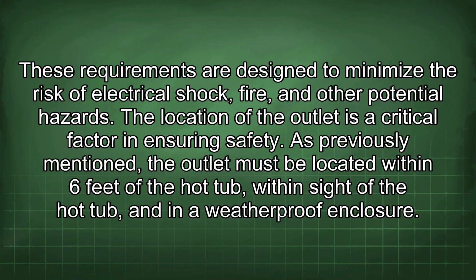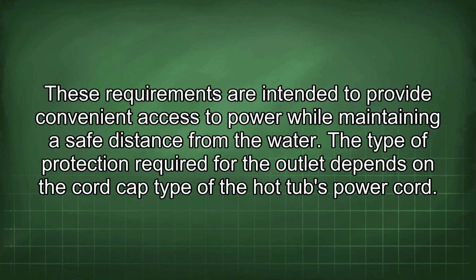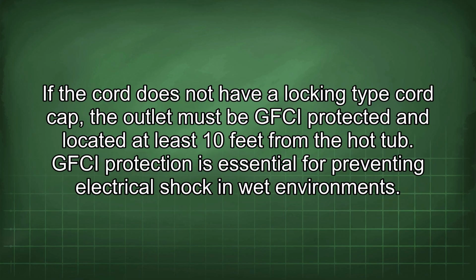The location of the outlet is a critical factor in ensuring safety. As previously mentioned, the outlet must be located within 6 feet of the hot tub, within sight of the hot tub, and in a weatherproof enclosure. These requirements are intended to provide convenient access to power while maintaining a safe distance from the water. The type of protection required for the outlet depends on the cord cap type of the hot tub's power cord. If the cord does not have a locking type cord cap, the outlet must be GFCI protected and located at least 10 feet from the hot tub.